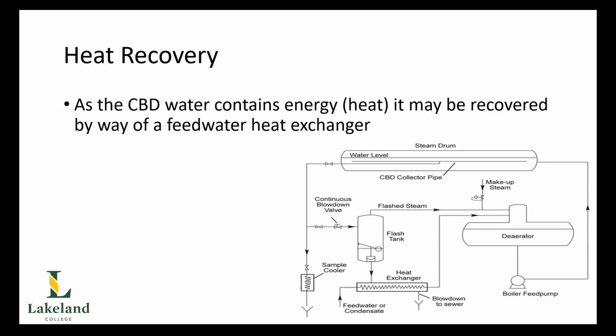Now, because we're removing hot water with regards to our CBD, and it's being removed usually continuously, that stream of water over a 24-hour period will be quite the volume. And that volume of very hot water will contain a lot of enthalpy, i.e. heat energy. So if you think about it, we're basically tipping all of that enthalpy down the drain. Well, that's quite a waste, and it represents a loss in efficiency.